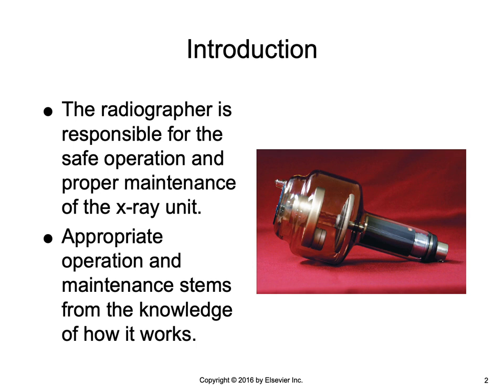The need for us to understand the x-ray tube is twofold. First, we must have a basic understanding of how the tube works to competently and safely formulate the exposure techniques, and we want to minimize the patient radiation dose as well. Second, we have to have an understanding that is very critical to extending the life of the tube and to avoid damaging it with too many heat units.